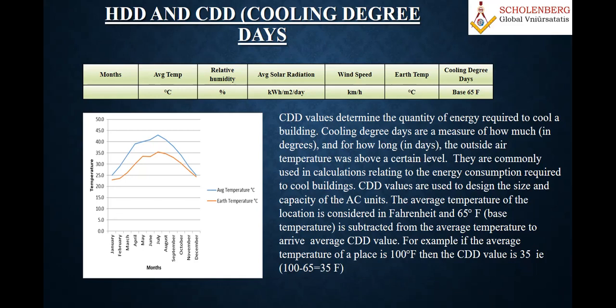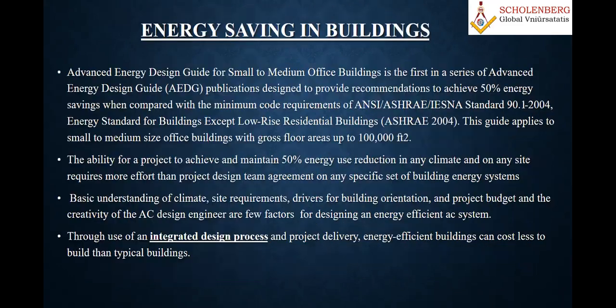Basically, the cooling degree days determine the quantity of energy required to cool your building. It is a measure of how much, and for how many days, the outside temperature was above a certain level, like a benchmark level. They are commonly used in calculations relating to the energy consumption required to cool buildings, the design aspect. So CDD values are used to design the size and capacity of the air conditioning units. On that basis only, I have taken this.